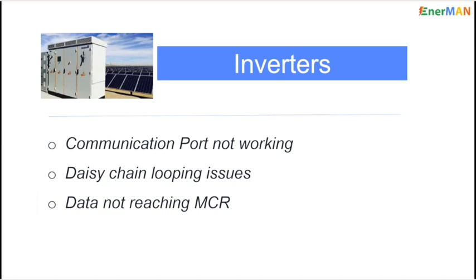As you know, most of the time communication ports are daisy chained, and we've seen a lot of looping issues here. When using fiber cables, switches, and media converters, many times the data from the inverter room doesn't reach the master control room, that is the MCR.